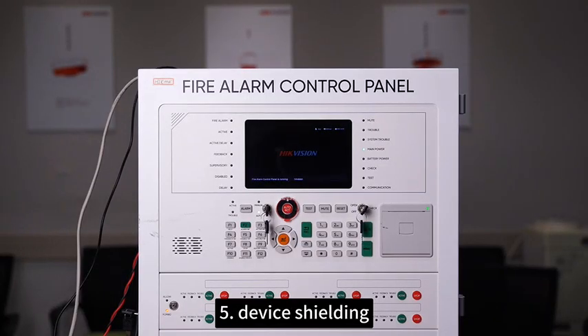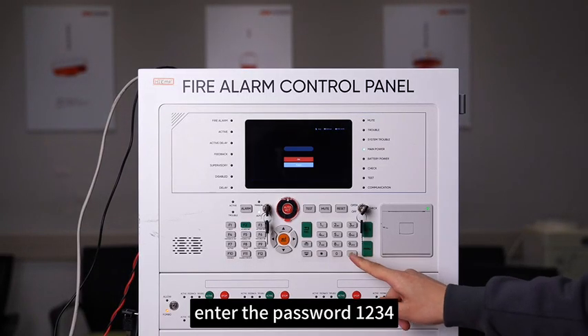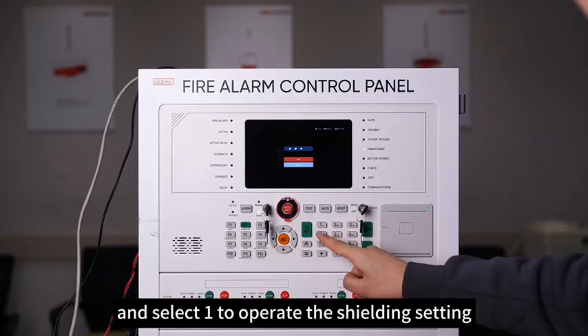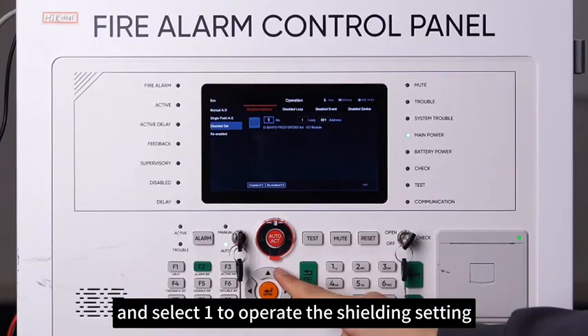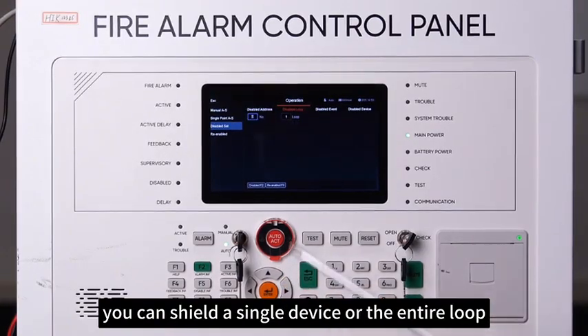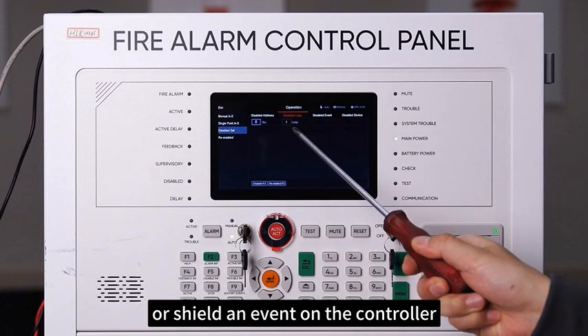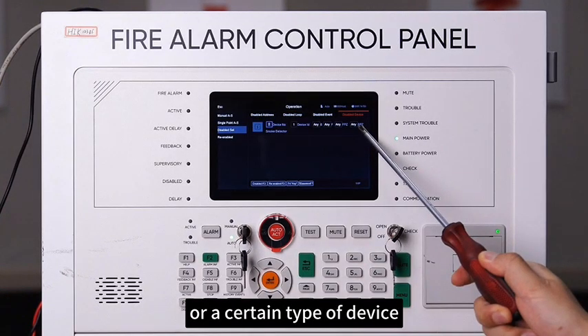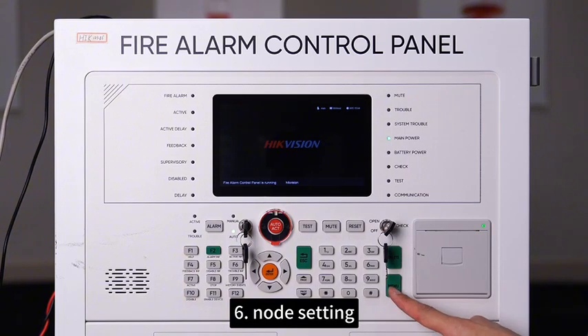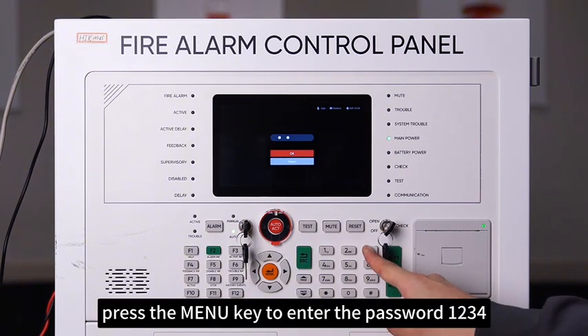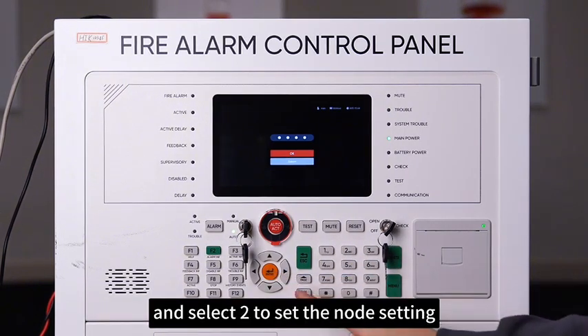Fifth, device shielding, press the menu key, enter the password 1234, and select 1 to operate the shielding setting. You can shield a single device or the entire loop, or shield an event on the controller or a certain type of device.